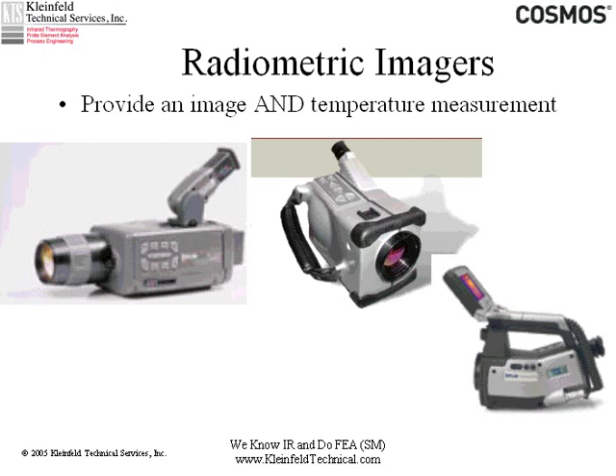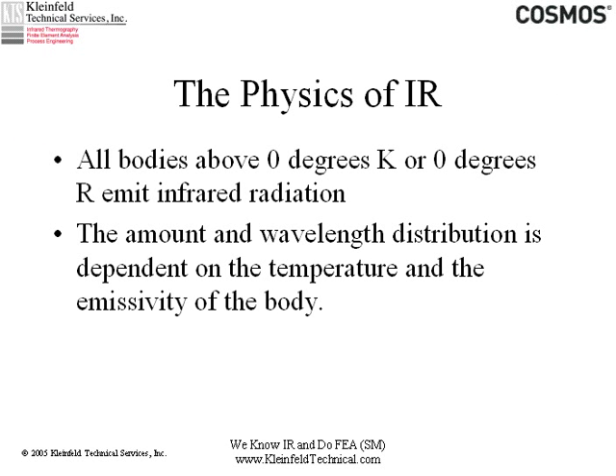An example of the equipment used — these are radiometric imagers. They provide both an image and temperature measurement. These are approximately the size of camcorders; you can see they are handheld, a larger and smaller piece of equipment. They're quite sensitive and quite accurate. The one on the left, which is a sample of the one I use, is rated at a sensitivity of 70 millikelvin — that's 0.07 degrees centigrade temperature sensitivity at 30 degrees centigrade. So it's good stuff.